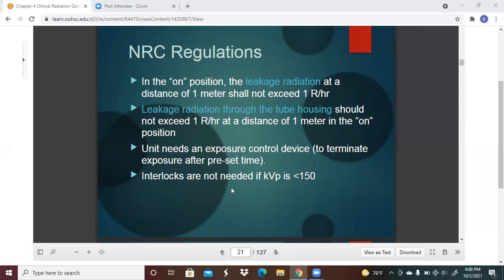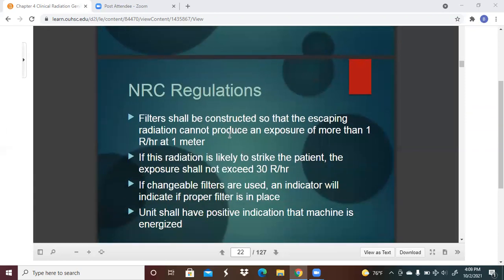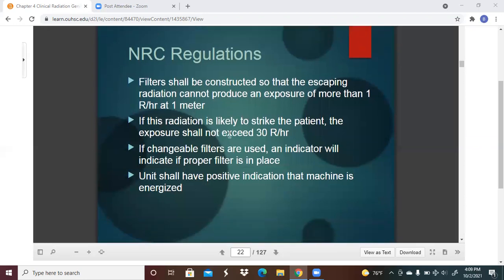The unit needs an exposure control device to terminate exposure after a preset time. And interlocks are not needed if the kVp is below 150. Filters shall be constructed so that the escaping radiation cannot produce an exposure of more than 1 Roentgen per hour at 1 meter. If this radiation is likely to strike the patient, then the exposure shall not exceed 30 Roentgen per hour.